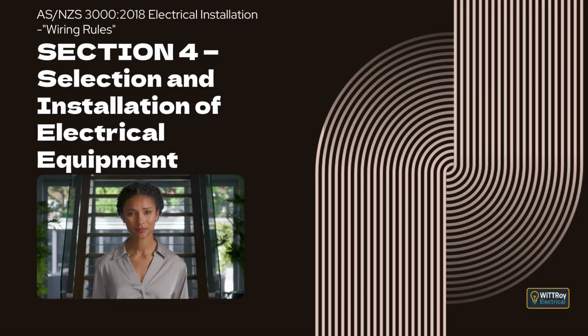Clause 4.10.2. Heating cables. This clause explains that heating cables must be installed so they do not come into contact with flammable materials. Where the system is designed to be embedded, the cables must be fully and properly embedded in the material they are intended to heat and must not be damaged by movement, flexing, or shifting of that material over time. It also explains that where heating cables are designed as trace heating, they must be installed so heat is effectively transferred to the surface or material they are attached to. In New Zealand only, this clause explains that in-floor and ceiling heating cables must be installed in accordance with NZS 6110. Clause 4.10.3, Isolating switches.